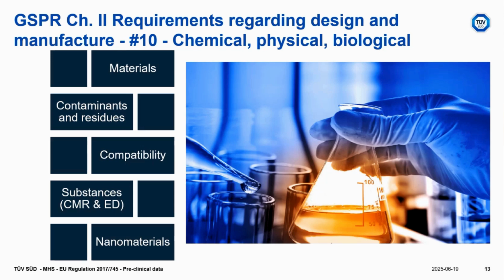There is a GSPR on the compatibility of the device with all the materials with which the device could be in contact. There is a new requirement on the substances, and especially the CMR and ED substances, where, depending on the content, there is an expectation of a very well-defined risk assessment by the manufacturer and the justification why certain materials are present in the device, with clear consideration also of the potentially sensitive patient population. So that's why this is also in correlation with the materials definition.